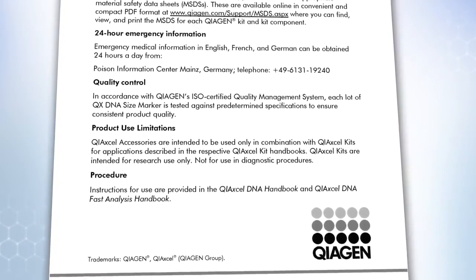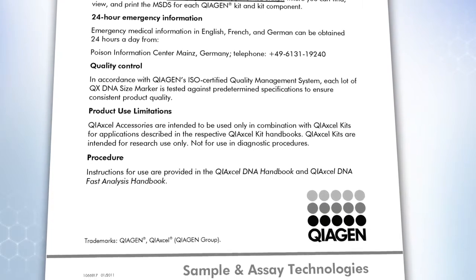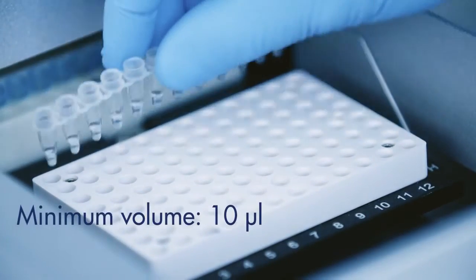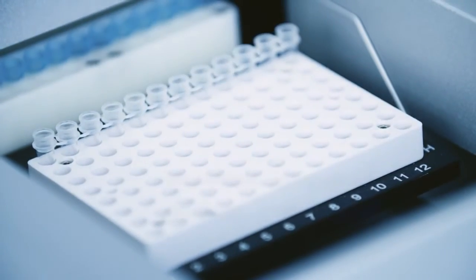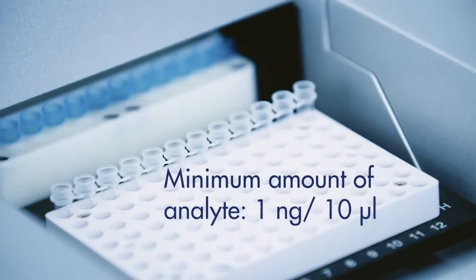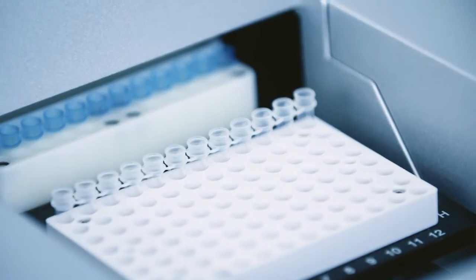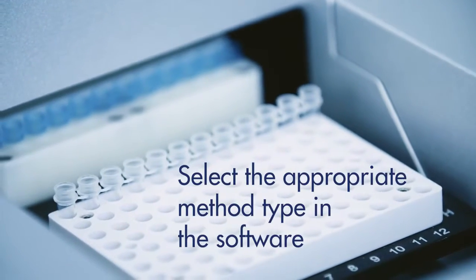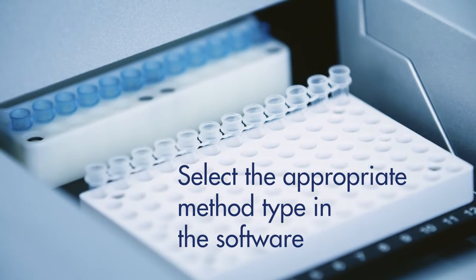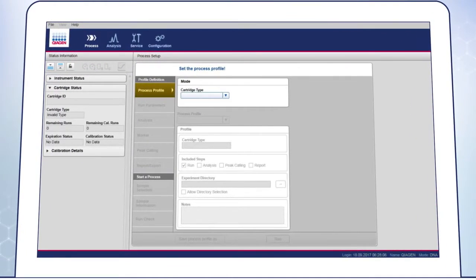For each run, a volume of at least 10 microliters of size marker is required. For the samples, a minimum volume of 10 microliters with a minimum amount of 1 nanogram analyte is required. In addition, it is important to select the appropriate method type in the software depending on the concentration of the samples. To start a run, first switch on the QIAxcel Advanced and start the PC and ScreenGel software. Then click on the Load Position button and load the buffer tray with buffers and markers and the samples onto the holder. Please double-check that all positions are correctly loaded.